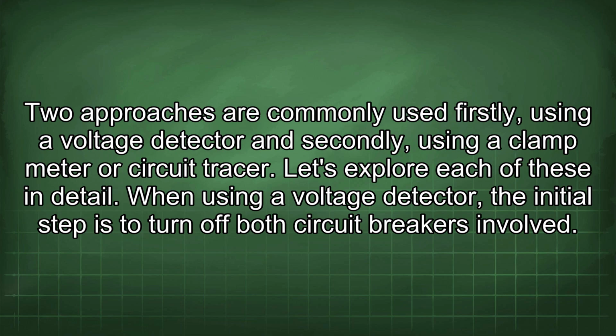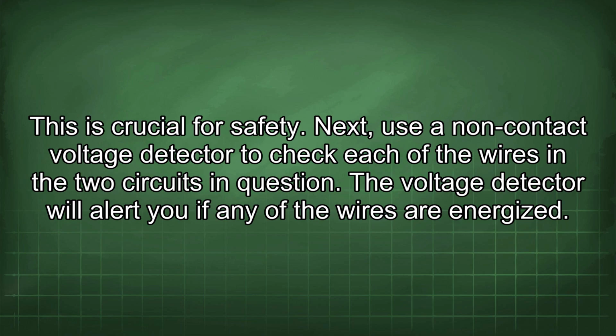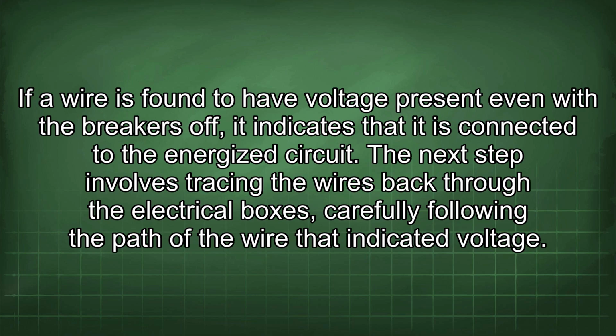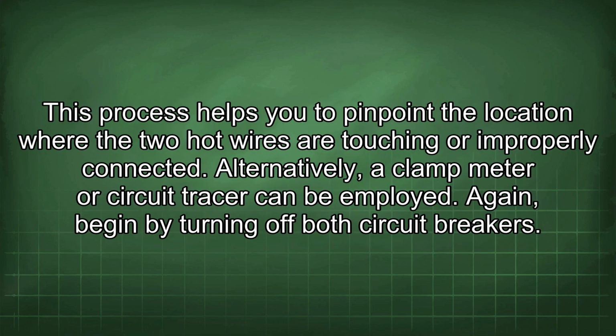When using a voltage detector, the initial step is to turn off both circuit breakers involved. This is crucial for safety. Next, use a non-contact voltage detector to check each of the wires in the two circuits in question. The voltage detector will alert you if any of the wires are energized. If a wire is found to have voltage present even with the breakers off, it indicates that it is connected to the energized circuit. The next step involves tracing the wires back through the electrical boxes, carefully following the path of the wire that indicated voltage. This process helps you to pinpoint the location where the two hot wires are touching or improperly connected.